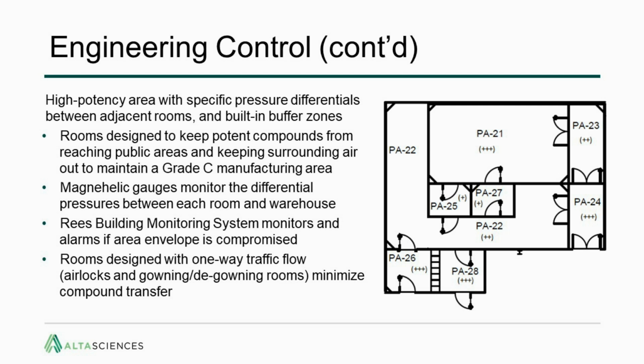There are magnehelic gauges to monitor the differential pressures between each room and the warehouse. But then we went one step further and put it on our building monitoring system, Rees, that instantaneously notifies us if the envelope is compromised, so we can take immediate corrective action.